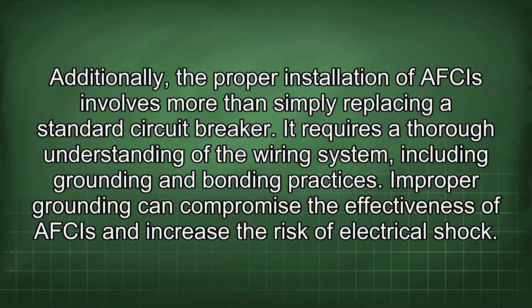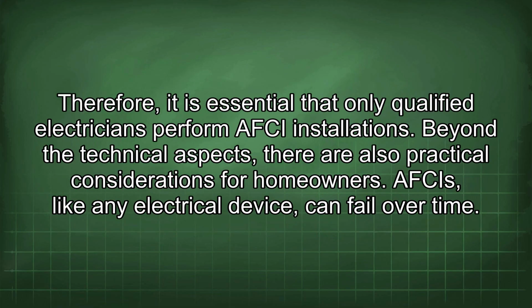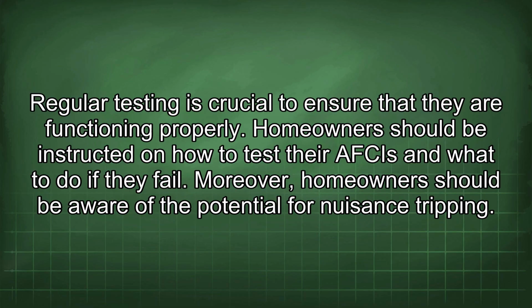Improper grounding can compromise the effectiveness of AFCIs and increase the risk of electrical shock. Therefore, it is essential that only qualified electricians perform AFCI installations. Beyond the technical aspects, there are also practical considerations for homeowners. AFCIs, like any electrical device, can fail over time. Regular testing is crucial to ensure that they are functioning properly. Homeowners should be instructed on how to test their AFCIs and what to do if they fail.